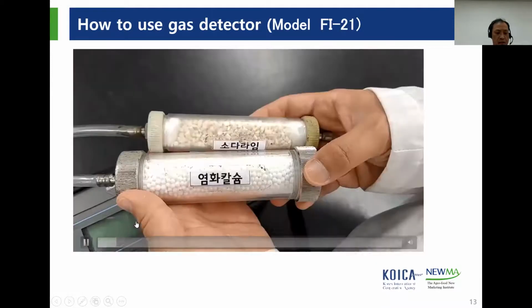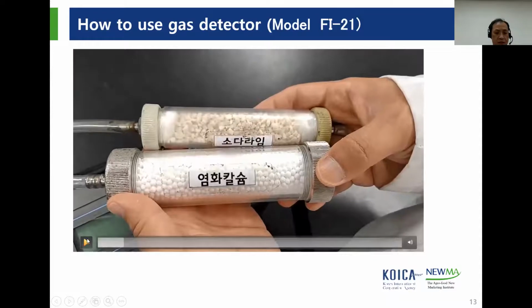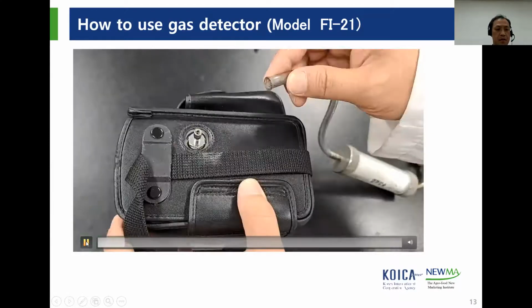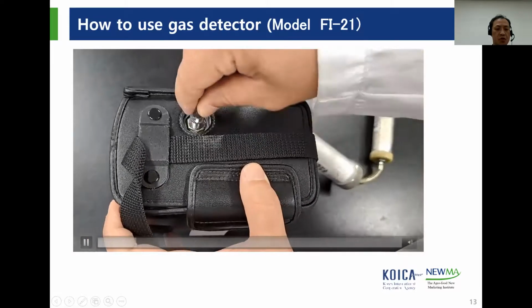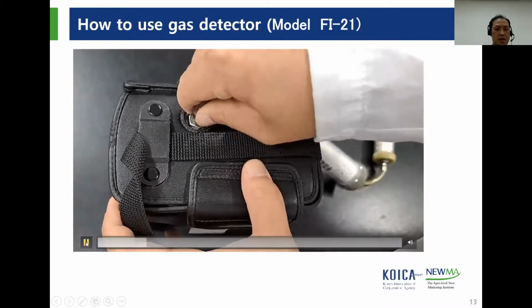FI21 is affected by carbon dioxide concentration. An absorbing tube should be attached to reduce the effect of carbon dioxide. That is why soda lime should be attached to the gas concentration detector. Connect the absorbers to the inlet of the gas detector.